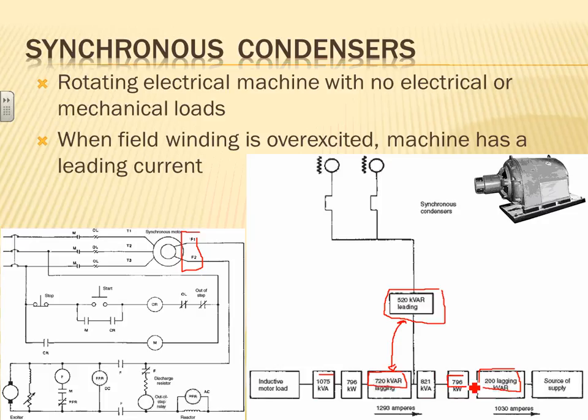And then with the existing 200 kVAR, with the existing 796 kW, it will get you an 821 kVA, which means, look at that, that's my favorite. Look at the reduction in the amps. My amps were 1293 here. By the time you added the capacitor, my amps got knocked down by close to 200 amps. So that's the concept of increasing the power factor by reducing the line current, which means utilities love you now, because you are paying for what you're consuming.